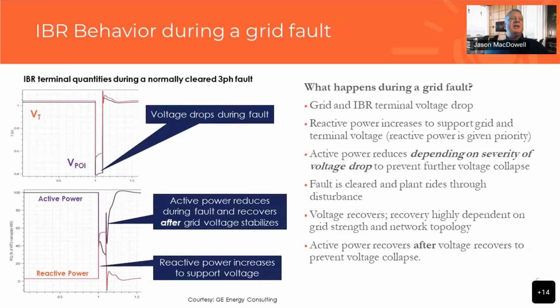So as the fault is happening, as you can see here, the voltage is depressed, active power is reduced, reactive power is prioritized so that we can boost the voltage, and the inverter-based equipment can ride through the event as is needed by that stabilizing reactive power, reactive current injection.